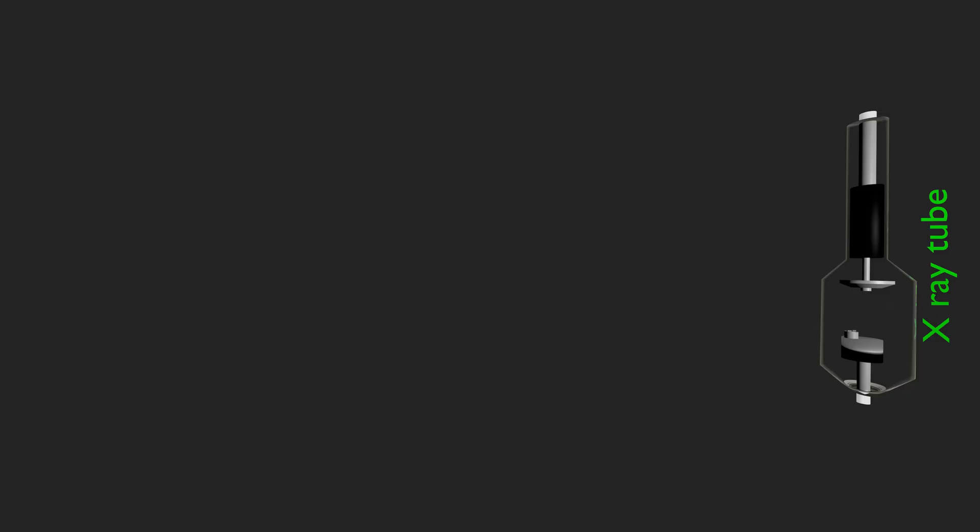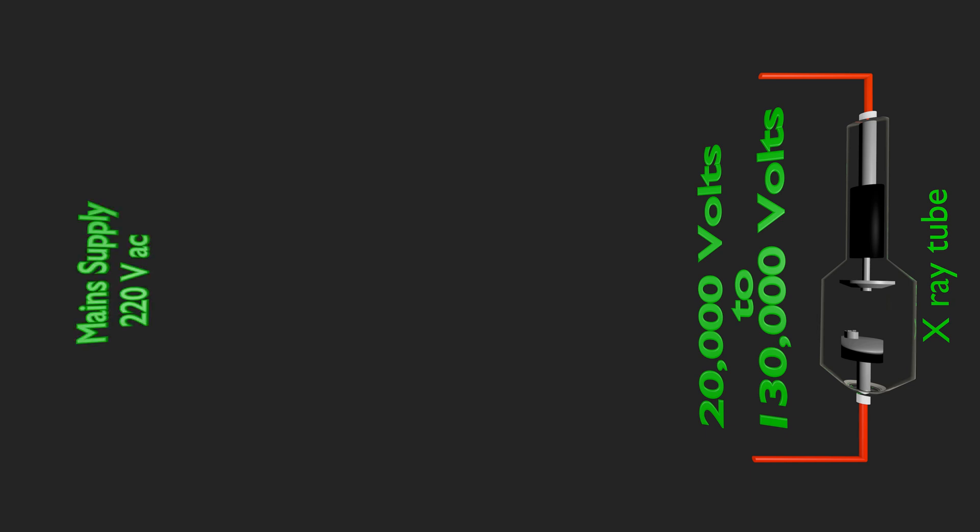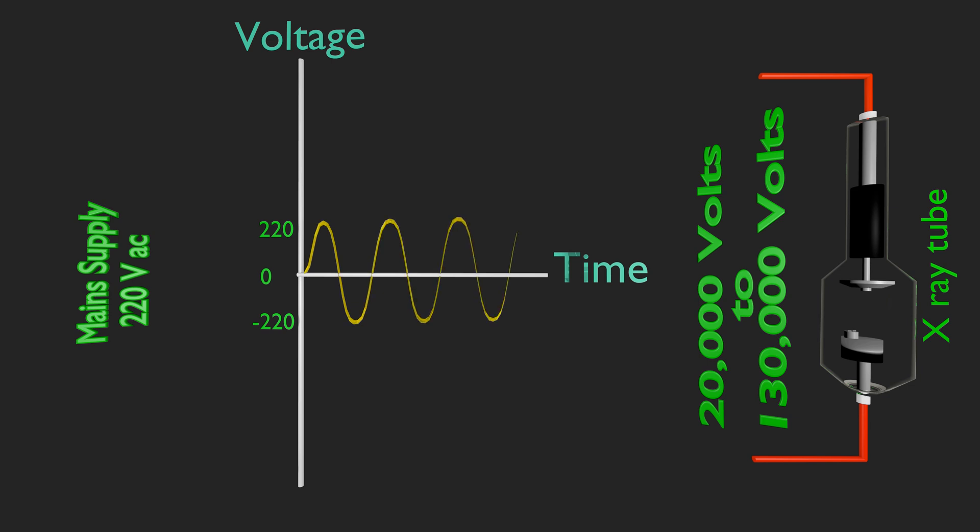X-ray tubes need an input voltage of 20,000 volts to 130,000 volts to be applied across its anode and cathode. Whereas, a single-phase mains supply is about 220 volts or three-phase power supply of 440 volts alternating power supply.